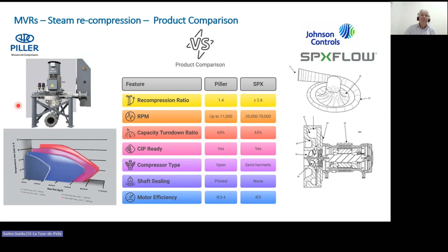So if you want a temperature increase of around 40 degrees, from 100 to 140 degrees, we would already need 4 machines in series, each of the steps adapted for the flow rate, for the pressure rating, etc. So we are also studying turbo compressors. There are two currently in discussion. One is SPX Flow, the other one is Johnson Controls. The advantage of turbo compressors is they can make a temperature lift of 20 degrees. So instead of having 4 steps like here, we would need only 2 steps of pressure increase or temperature increase with the turbo compressors. So not yet decided which way we will go, but we will certainly go with steam compressors, either the left side or the right side, not yet fully decided.